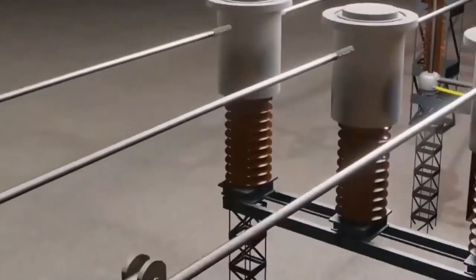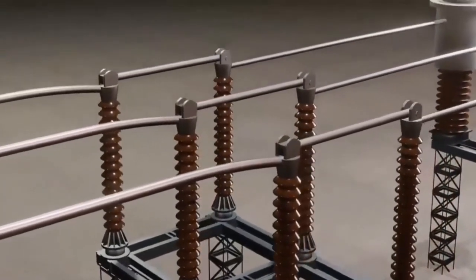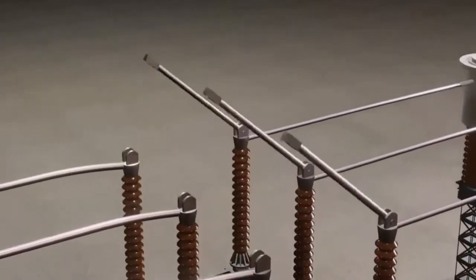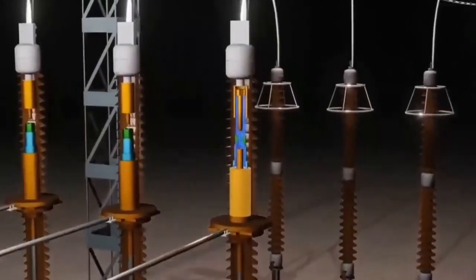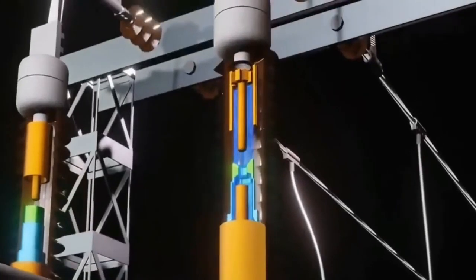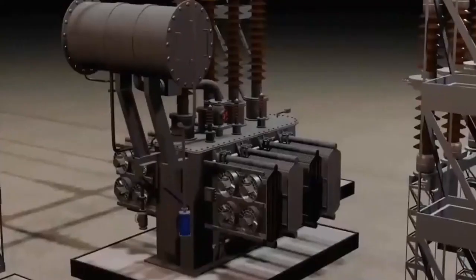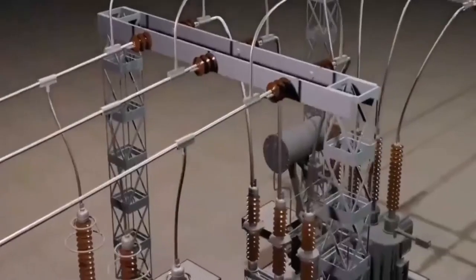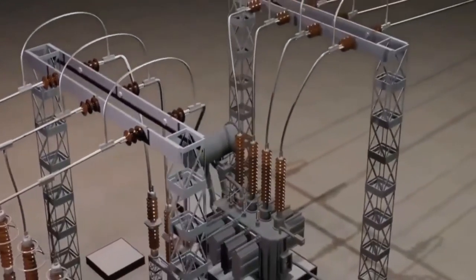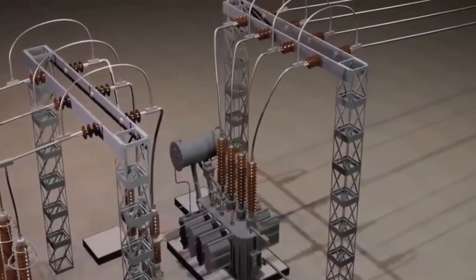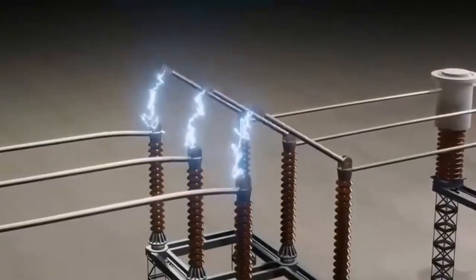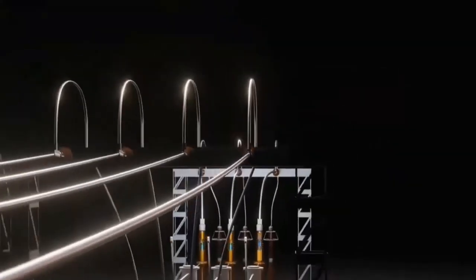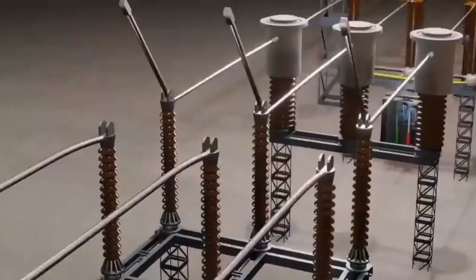Additionally, for added safety measures, all these contacts need to be opened to achieve double security. Here is an issue. Suddenly disconnecting the high voltage transmission line will cause a current surge. Since transformers are usually connected behind the circuit breaker, the sudden return of a powerful current can lead to voltage instability, even damaging the transformer. So unless there is a major accident, high voltage transmission lines are generally not disconnected. So how do you reconnect the transmission line now?